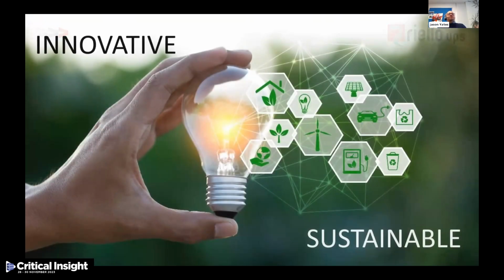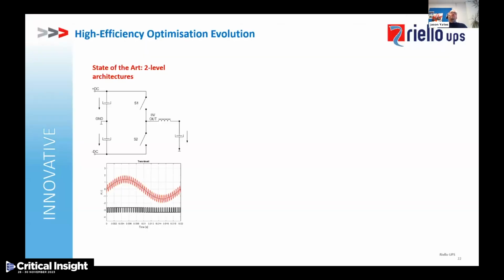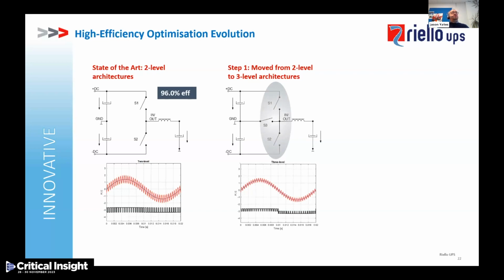Let's move on. Okay, so how have we got to where we are today? Well, many, many years ago, we used to produce UPS systems using what's referred to as a two-level architecture. Now, the two-level architecture, back in the day, has been a stable design of UPS for many, many years, but it could only achieve an efficiency in reality of up to around 96% at best. We then made the move from the two-level architecture into the three-level architecture. The benefit of the three-level architecture is that we could push the efficiency up to 96.5%.